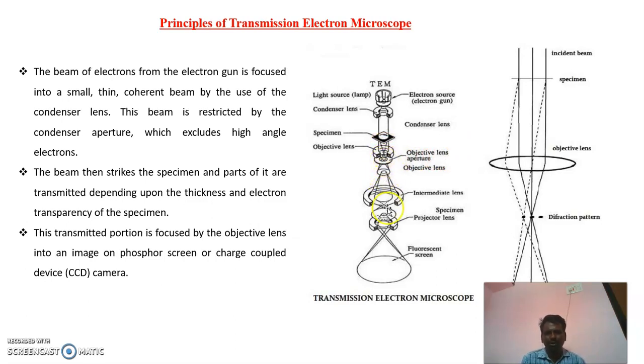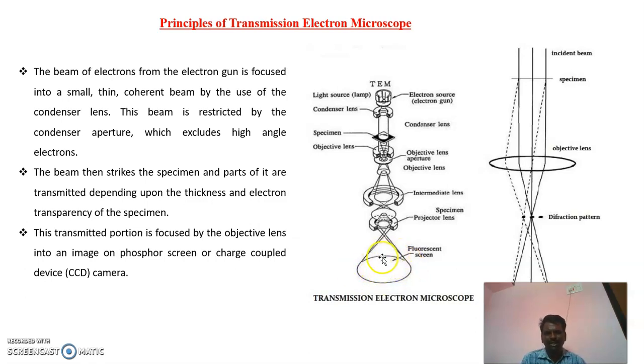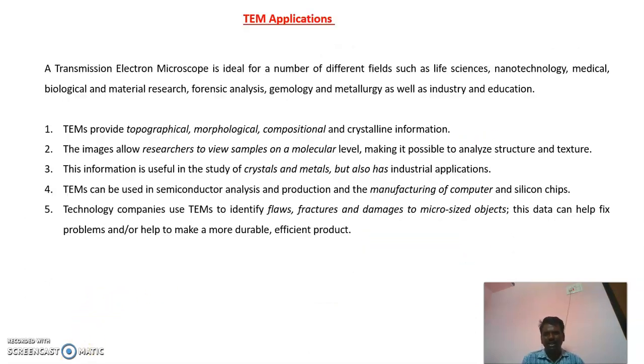The image then goes down to the phosphorous screen, generating light on it. The dark area of the phosphorous screen corresponds to a lesser number of transmitted electrons, and the lighter area of the phosphorous screen corresponds to highly transmitted electrons. This is the working principle of TEM.